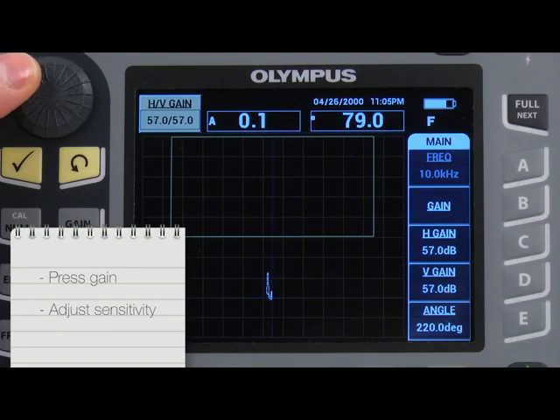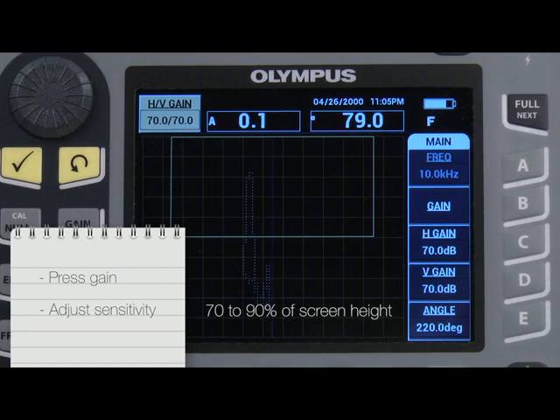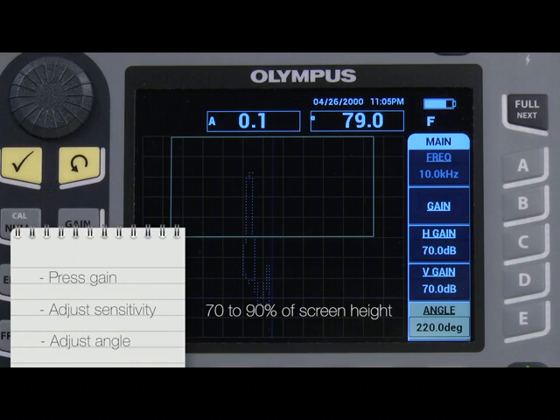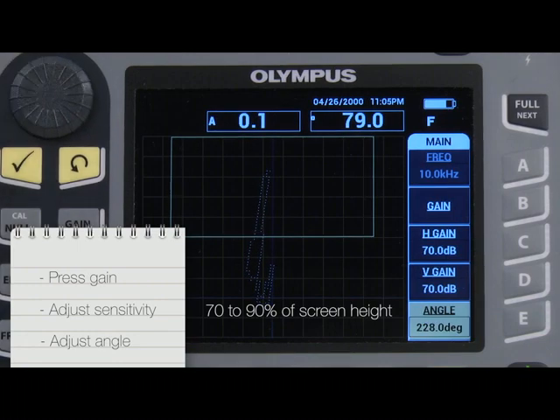Slowly scan over the simulated disbond while maintaining constant pressure. When done, press the Freeze key. Press the Gain key and adjust the sensitivity to have the disbond at 70-90% of the full screen height. If needed, adjust the angle of the signal. The basic calibration is now complete.